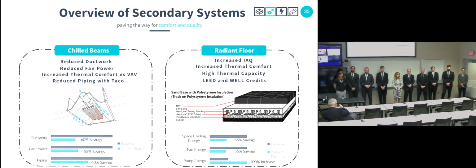The radiant flooring is in the track and field and practice field area. This hydronic system is known for its increased thermal capacity, making it very efficient. It also increases the indoor air quality in the space since you don't have large CFMs moving allergens and pollutants in the air. Due to there not being a concrete slab in the practice field area, a different construction process had to be thought of. So Mechanical utilized a system similar to what is shown, utilizing the radiant flooring within a sand bed underneath the turf. As you can see below, the systems allowed us to have savings in ductwork, fan power, space cooling energy, and fan energy.